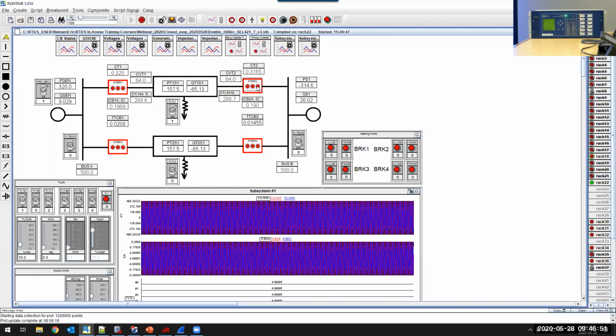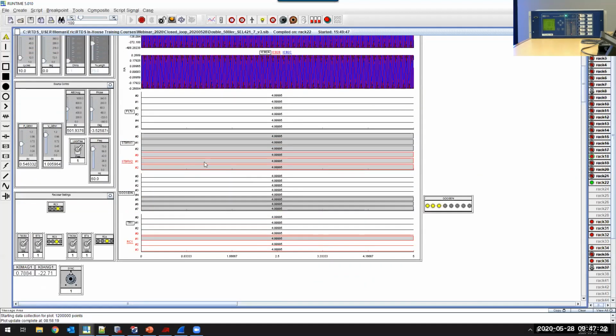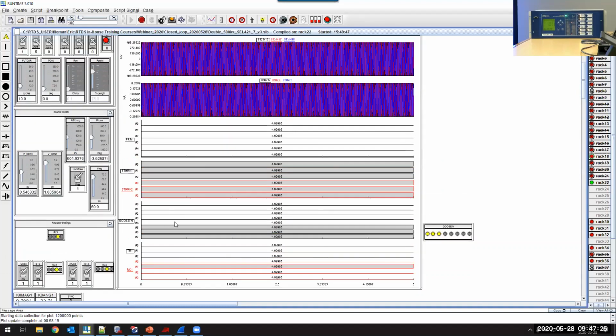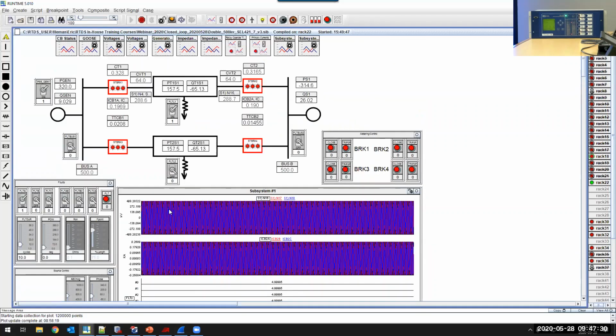So we expect to observe that this bit here, which represents A phase, will be open and then reclosed. So this light will be turned off and turned on again. It will change to green to represent an open state, and back to red to represent a closed state again. After I click the fault, we should hear a click from the relay as well, and we can observe the changes here, and also see the incoming GOOSE messages status, and compare that with the relay as well.